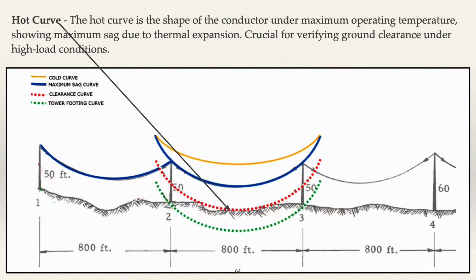Hot curve. The hot curve is the shape of the conductor under maximum operating temperature, showing maximum sag due to thermal expansion. Crucial for verifying ground clearance under high load conditions.